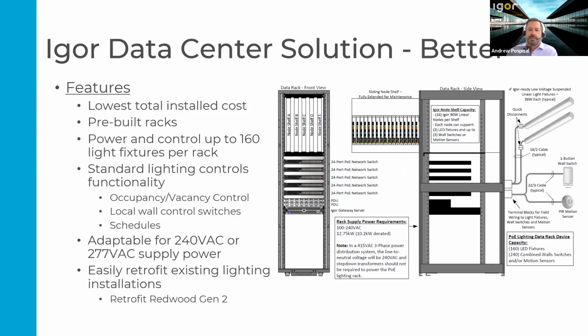These, based upon typical 36-watt fixtures, each of these racks can support up to 160 fixtures per rack. So if you're looking at, say, 75 square feet up to 100 square feet per fixture, you're looking at 12,000 to 16,000 square feet. Sorry, I tried to do the math beforehand. Hopefully I got that right. So a decent coverage area of lighting per rack. And these racks can be installed in electrical rooms, data closets, really wherever the designated space is, and obviously within proximity of the fixtures and sensors they would be serving.